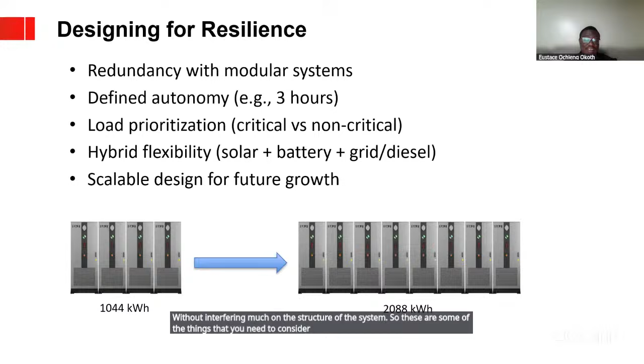When you look at the whole solar PV system structure, you find battery is the one that still has the highest cost. So defining your critical loads is very important. This helps a lot in also reducing these hours of autonomy, or increase the hours of autonomy for the critical loads, versus having both critical and uncritical load being supplied by the battery. The other thing is flexibility, and that's now come handy of whether you're going to use the hybrid inverter or whether you're going to use the AC coupled solution. Then the other thing is to look at scalability in future. Can you be able to increase the capacity without interfering much on the structure of the system? So these are some of the things that you need to consider when designing a resilient mini grid system.